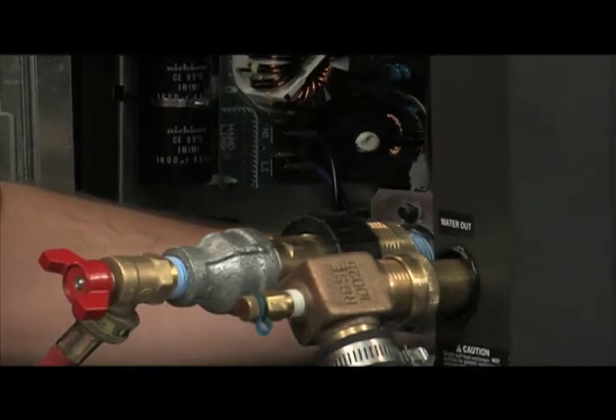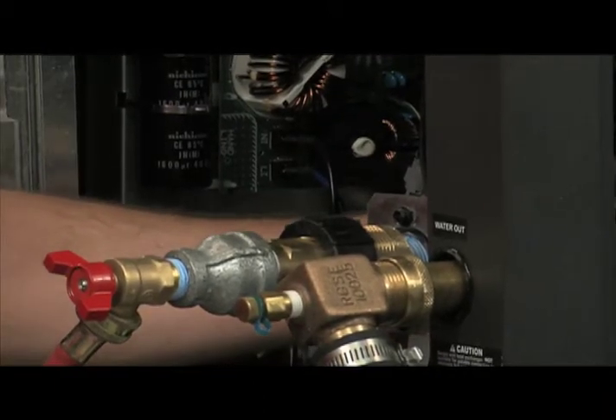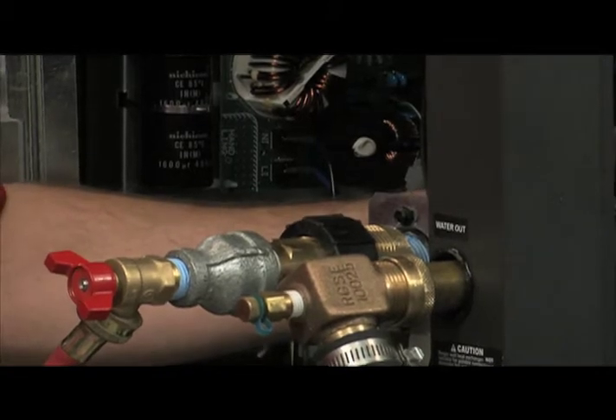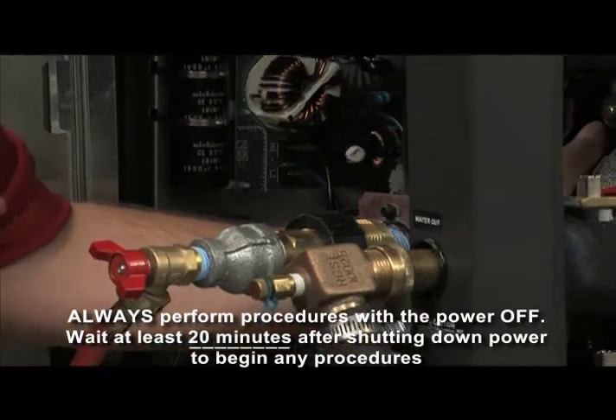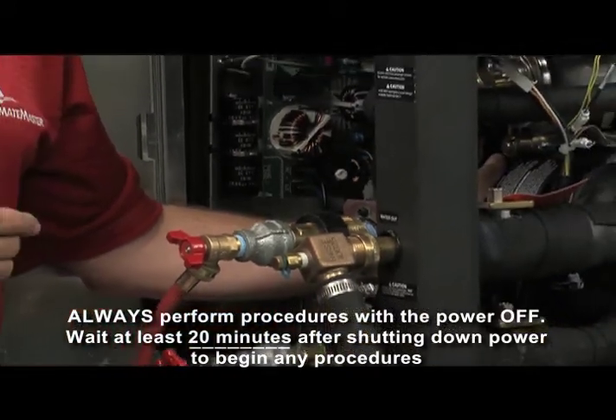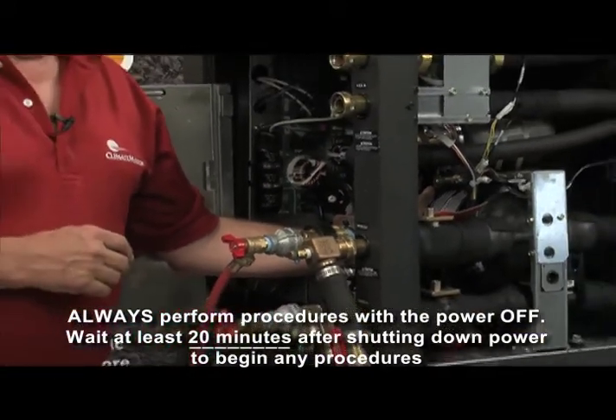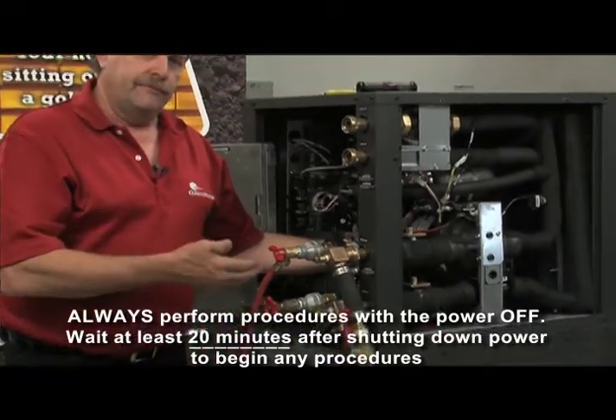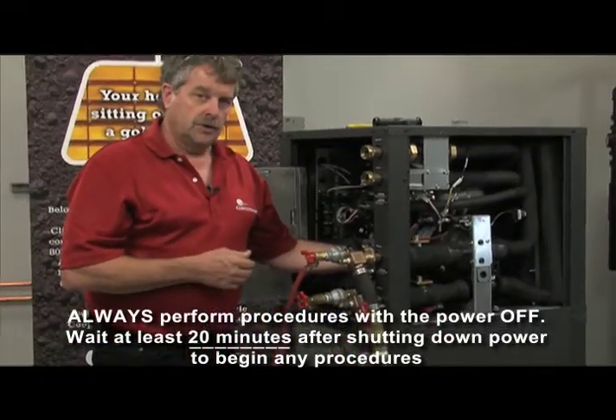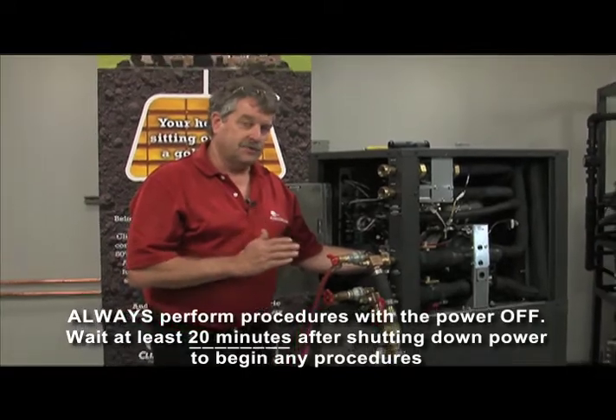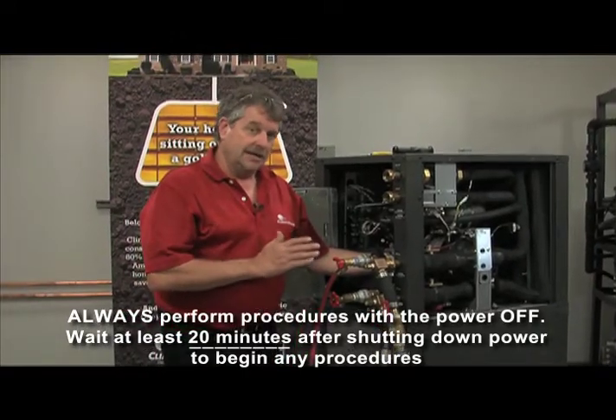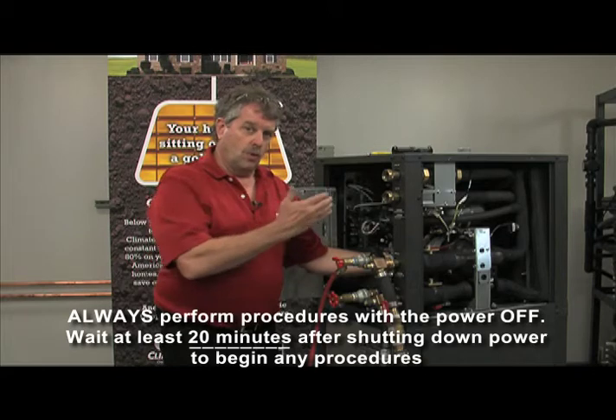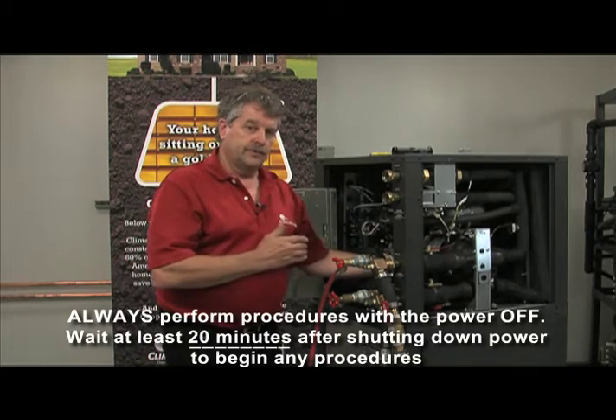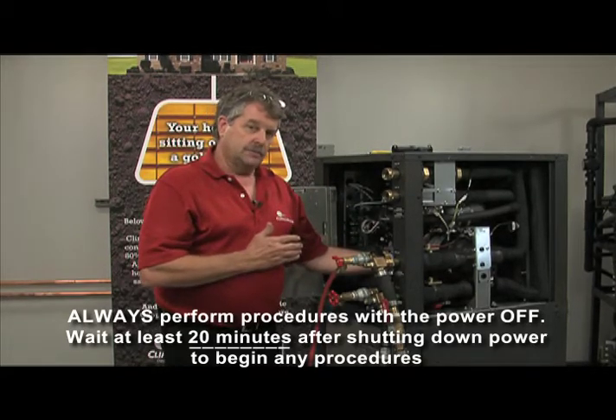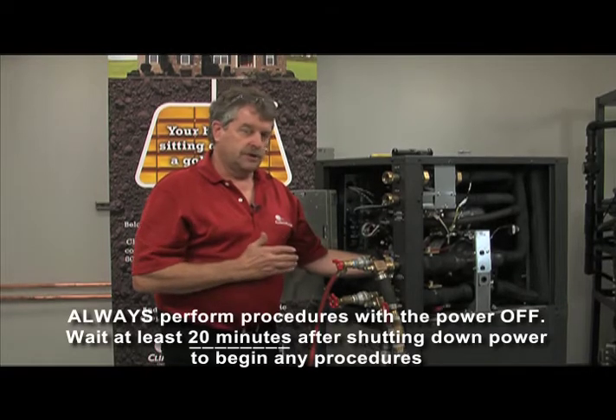So if we need to remove the pump, which is what I'm going to do, it's just going to be that ECM power head. Now, reaching in this box, guys, I've had the power off to this particular model. This is a Trilogy unit, and the power's been off for over 20 minutes, making sure that we have full discharge of our inductor and our capacitors. Safety first, you won't like the bite you get by shortcutting that. So we're working inside the cabinet here, on the fluid side. Make sure that power has been off for a good solid 20 minutes before you attempt any of this.